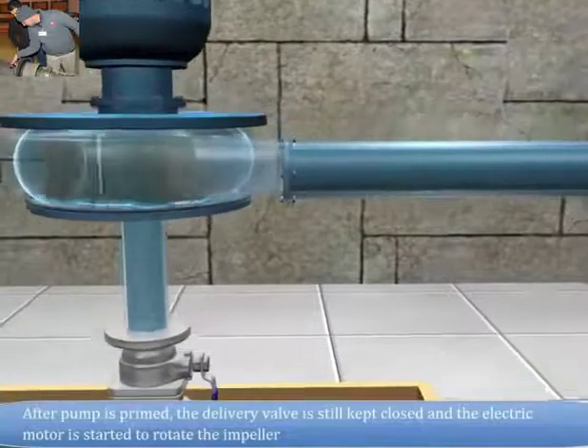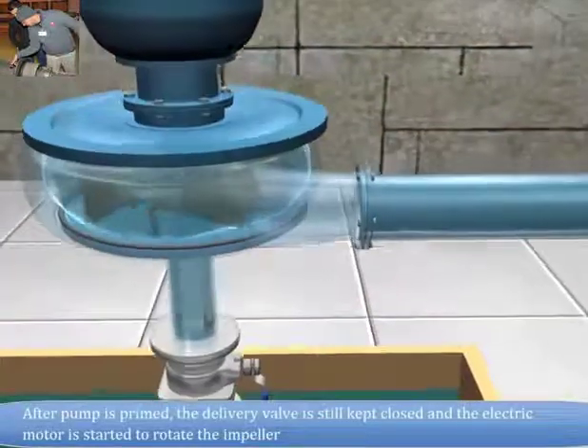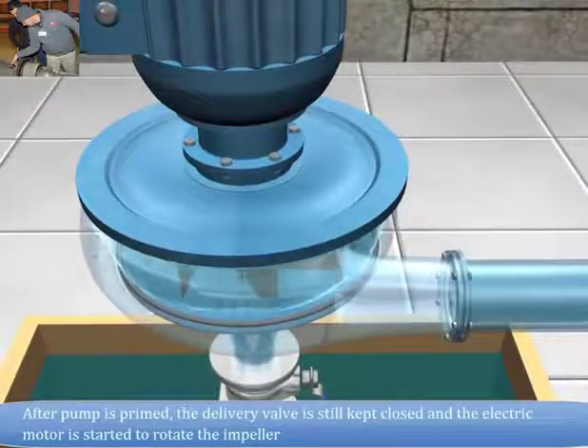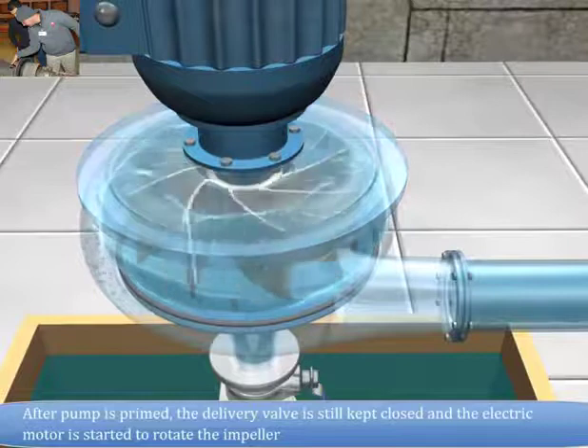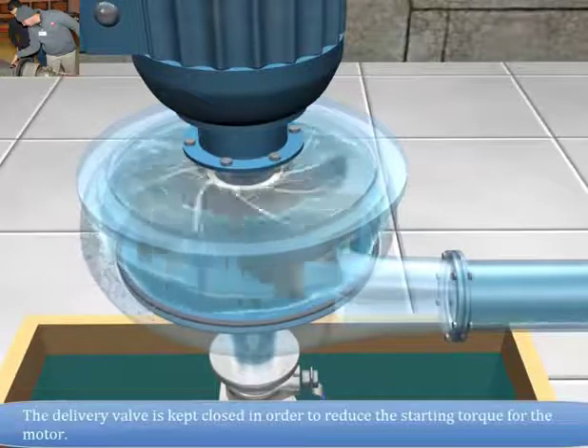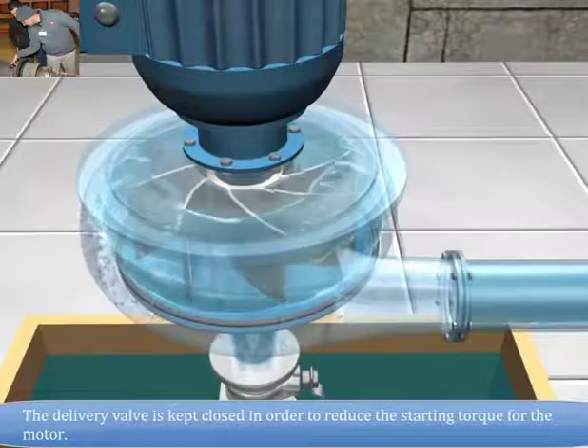After pump is primed, the delivery valve is still kept closed and the electric motor is started to rotate the impeller. The delivery valve is kept closed in order to reduce the starting torque for the motor.